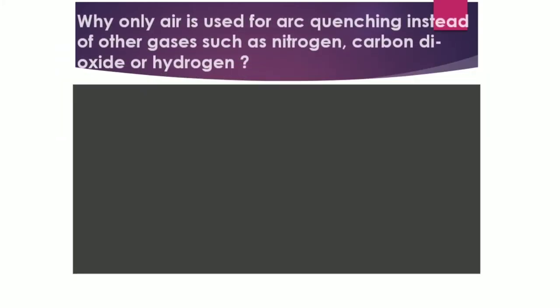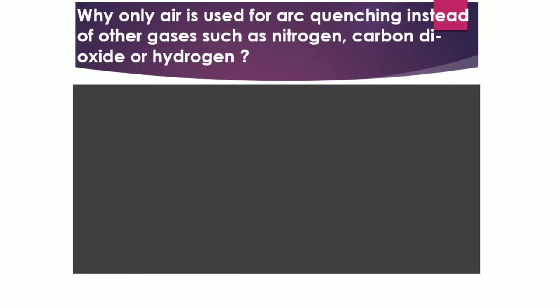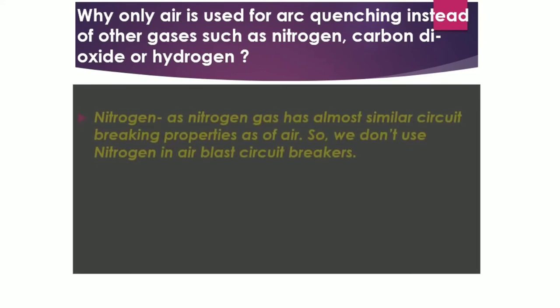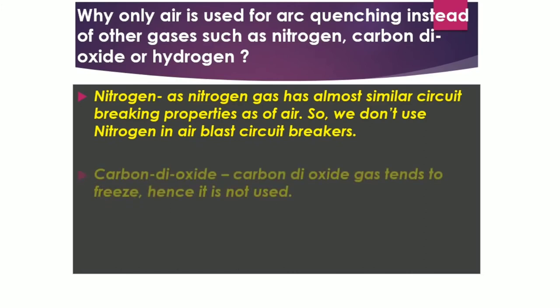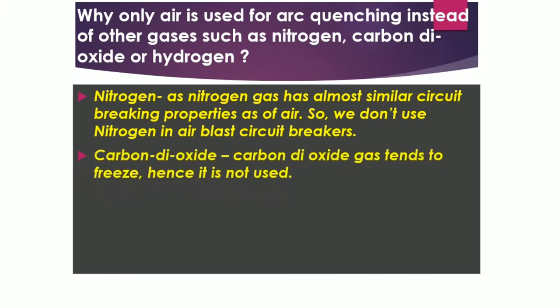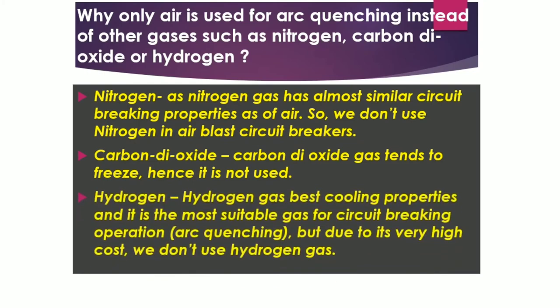In an interview you may be asked why air is used for arc quenching instead of other gases like nitrogen, carbon dioxide, or hydrogen. The answer: nitrogen has almost similar circuit-breaking properties to air, so it offers no advantage. Carbon dioxide tends to freeze. Hydrogen has the best cooling properties and is most suitable for arc quenching, but its cost is very high, so it is not preferred.